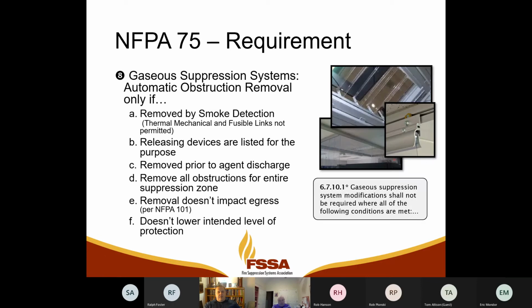If we're not going to modify the system and drop nozzles into that, and we're going to depend on automatic obstruction removal, then basically it's the same thing. Remove by smoke detection, same as sprinklers. Devices must be listed for the purpose. Remove prior to agent discharge. That's the only thing that's different. Remove all obstructions from the entire zone. Removal doesn't impact egress, and it shouldn't lower the intended level of protection. So if you're going to remove things before the gas dumps, instead of modifying and putting nozzles in the new volumes, that's what you've got to do.